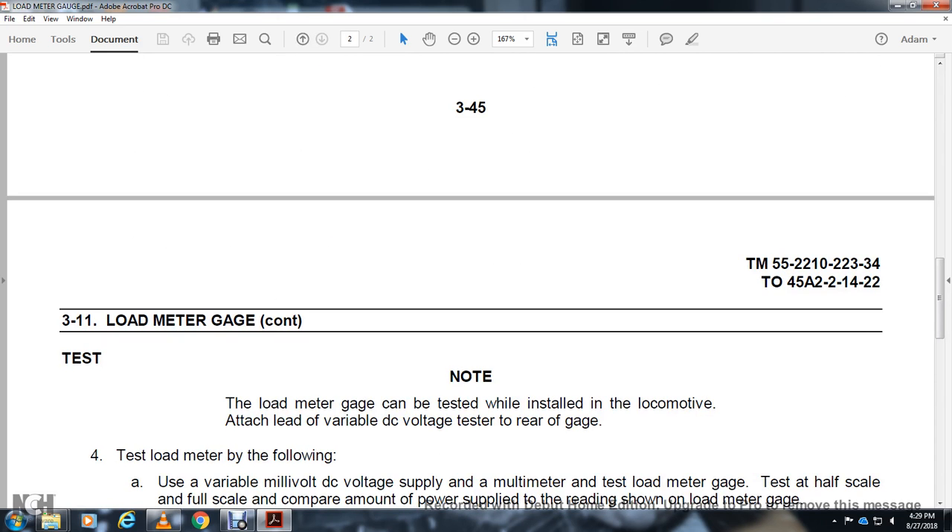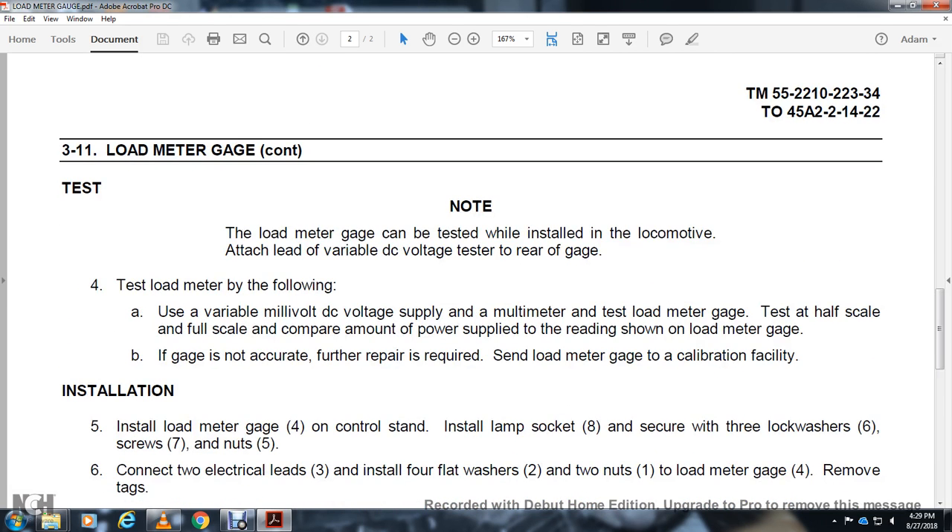Note: the load meter gauge can be tested when installed in the locomotive, attached with the variable DC volts supply to the rear of the gauge. Test load meter by the following: Variable millivolt DC volts supply and multimeter — test load meter gauge at half scale and full scale. Compare the amount of the power supply with the reading shown on the load meter gauge. If the gauge is not accurate, repairs are required; send the load meter gauge to the calibration facility.